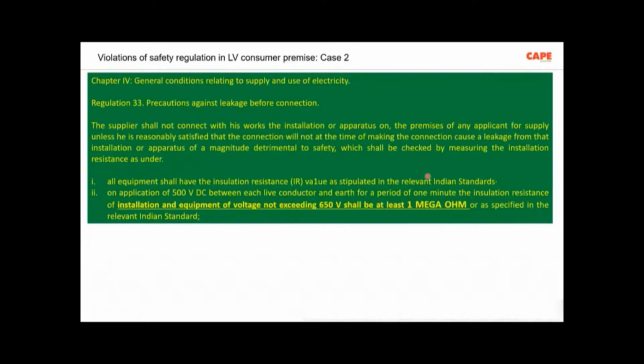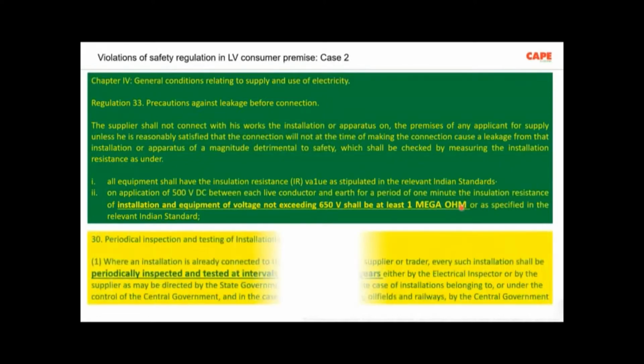case 2, Regulation 33. Regulation 33 of the Central Electricity Authority Safety Regulation says, you can read the underlined part: installation and equipment of voltage not exceeding 650 volt shall be at least 1 mega ohm. What is it? This is the minimum insulation resistance required in an electrical installation. 1 mega ohm between phase conductors to earth, and between neutral conductor to earth. You have to disconnect the neutral and earth link, and you are supposed to measure the insulation resistance, and within your installation 1 mega ohm is the minimum insulation resistance required.